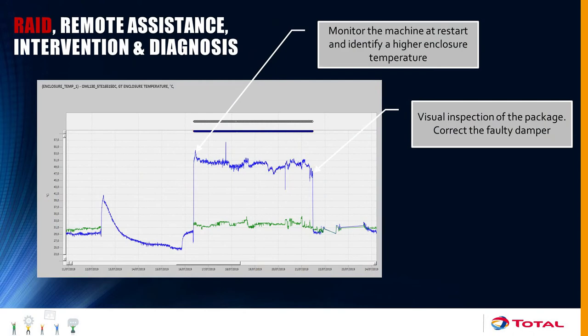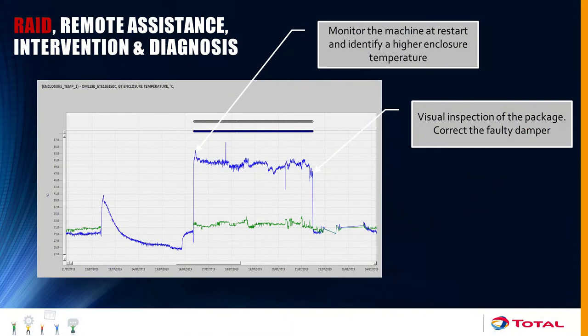Another very recent example from July — cases I'm working on right now. After a shutdown, the machine restarted and there was a severe change in enclosure temperature from this gas turbine. This is not normal, but there was no alarm and no trip or emergency shutdown from the temperature monitoring. We recommended our operator to have a closer look at this machine. They found a damper in the ventilation system that was faulty and had remained closed, meaning the cooling of the machine was not done properly, leading to an increase of temperature inside the enclosure.